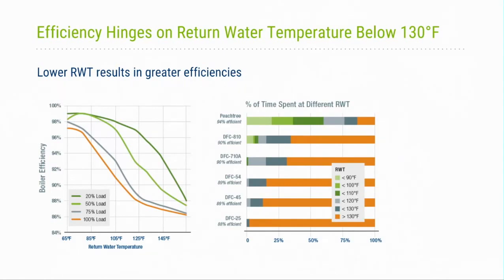And so that's a key consideration, and one of the takeaways is that if you're going to pursue condensing boilers, you need to ensure that you're getting those return water temperatures down as low as possible.